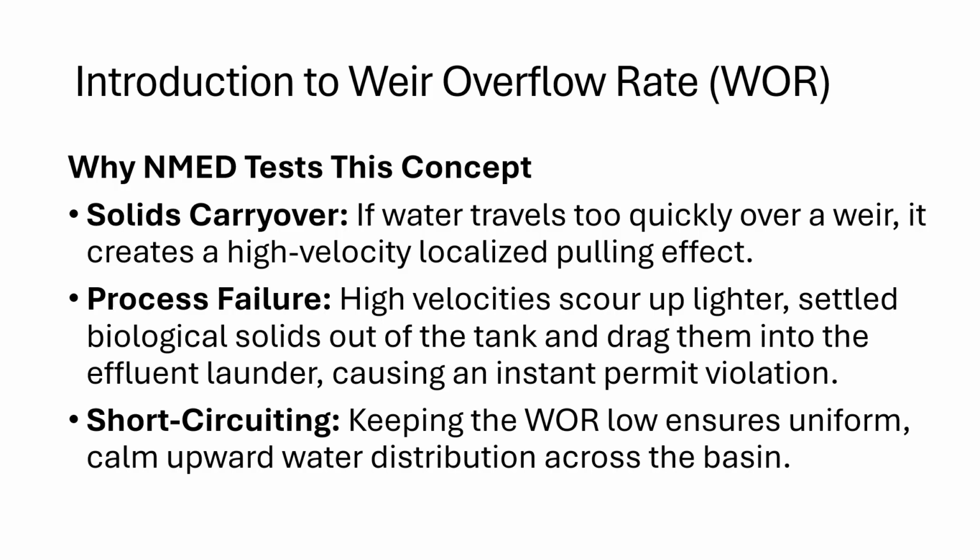In addition, keeping that weir overflow rate low is going to make sure that you have a calm water distribution across the basin, and it's going to prevent short circuiting. So the slower we move the water into the basin and push it out through those weirs, the slower that velocity, the less likelihood that we're going to have short circuiting take place.